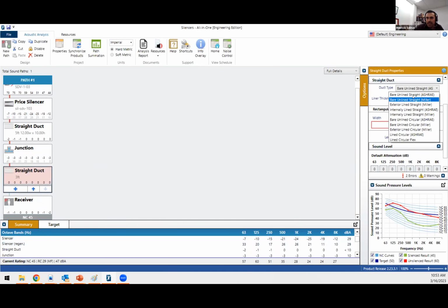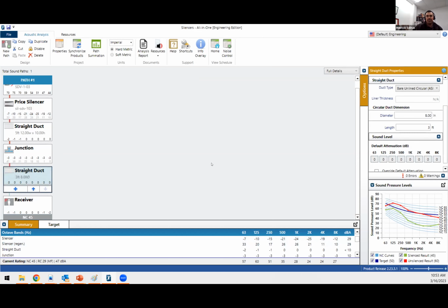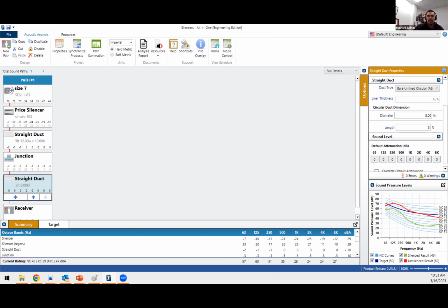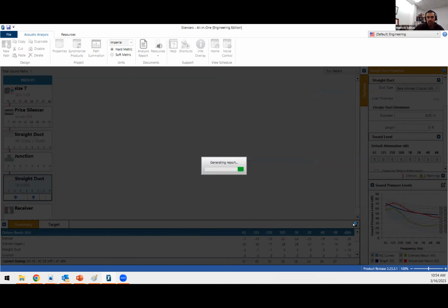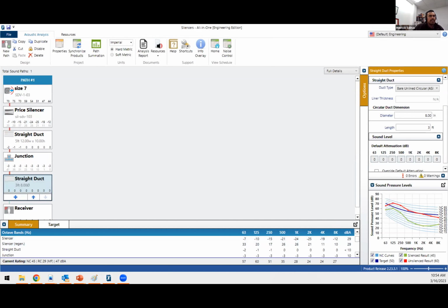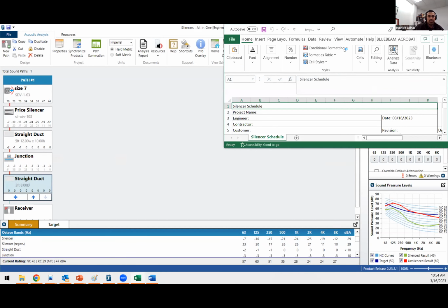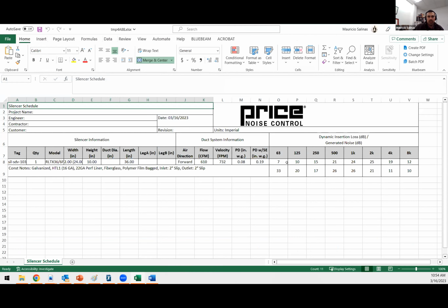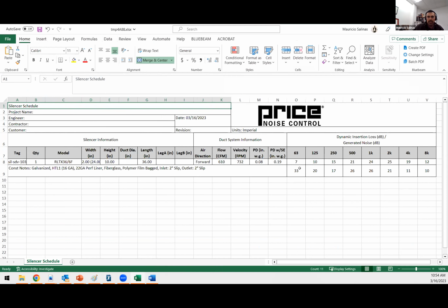And this is a circular duct, so you're at NC 45. And the cool thing is that now, if you did this with every terminal unit, with every rooftop unit, with one click of a button, you can create a report with all your assumptions. It literally takes seconds to load up. Right away, it's going to give you a schedule that you could put in your drawing as basis of design, with all the information to get you to that NC level, NC 45, with maximum generated noise values, right?